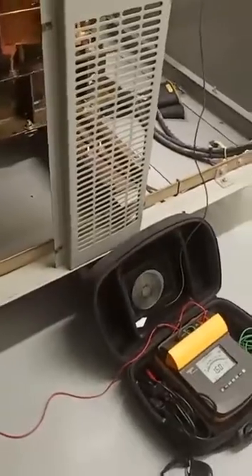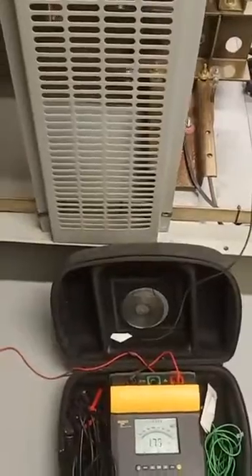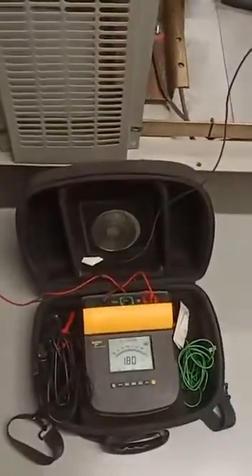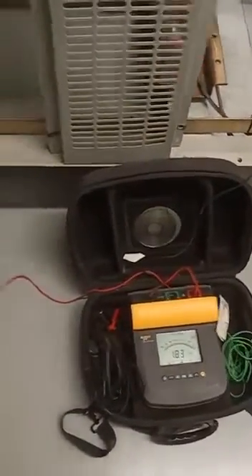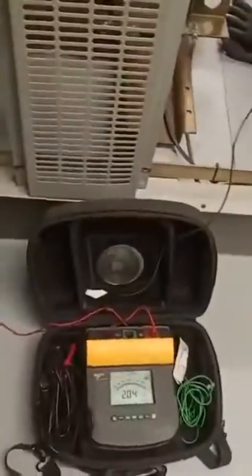So we will continue up to 10 minutes to find out the PI value. Polarization index is the ratio of the megaohm value after 10 minutes divided by the megaohm value after 1 minute. So we have to check the 10 minute value and divide it by the 1 minute value. This polarization index gives an indication of the buildup of moisture or dirt.